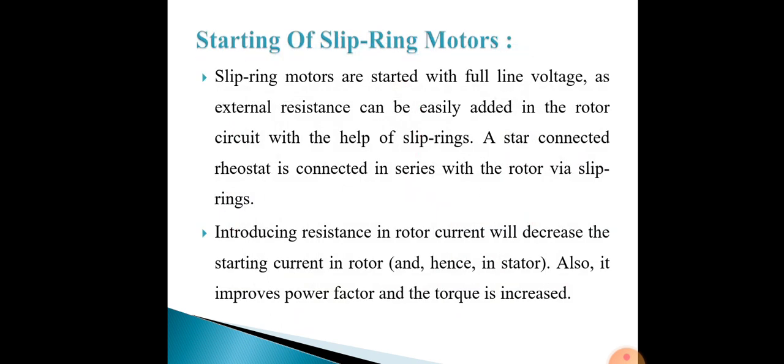Next is the starting of slip ring induction motors. In a slip ring induction motor, the resistance in the rotor circuit will decrease the starting current in the rotor. It also improves the power factor, and the torque is also increased by using slip ring motors. Slip ring induction motors are started at full line voltage, and external resistance can be easily added in the rotor circuit with the help of the slip rings.